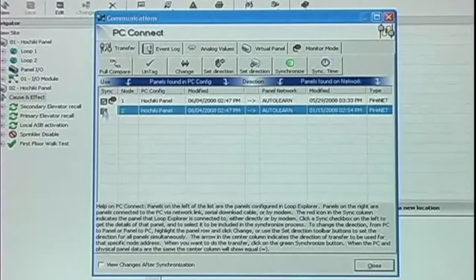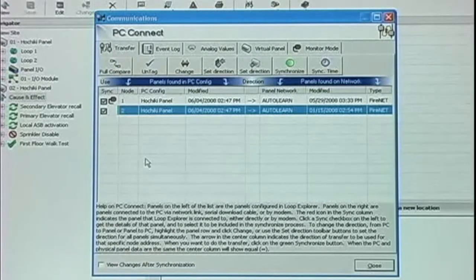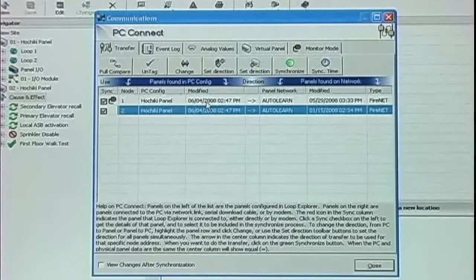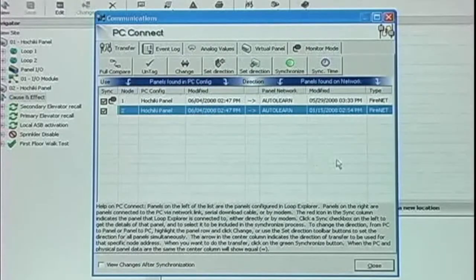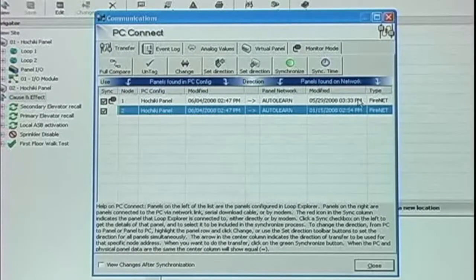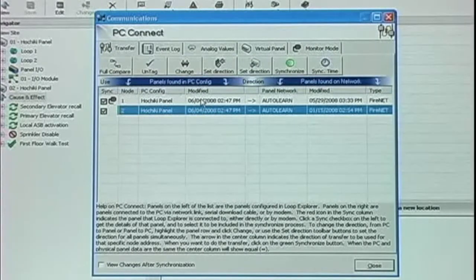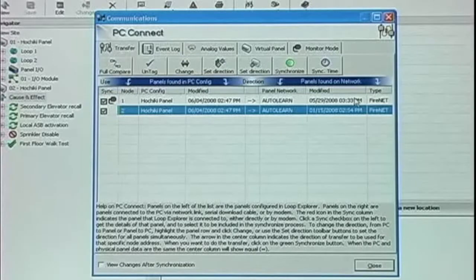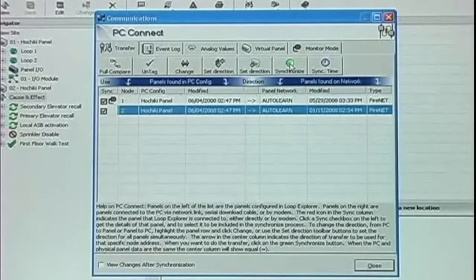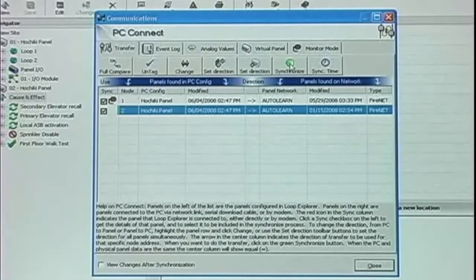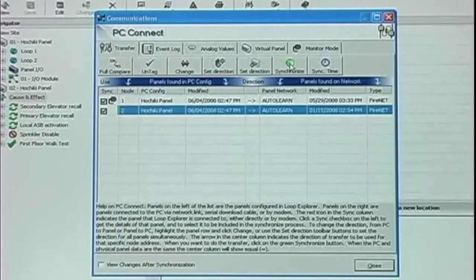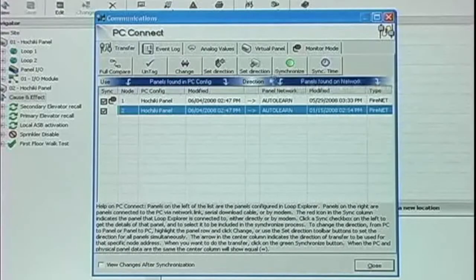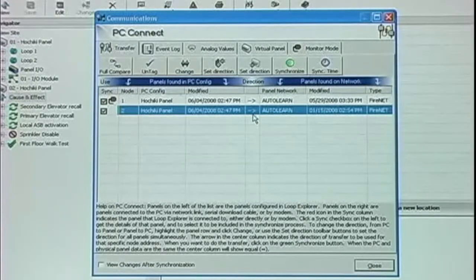When we check the sync box for each of the nodes, Loop Explorer compares the date and time stamp between the configuration in the PC and in the panels. When we click the Synchronize button, Loop Explorer will automatically send the data in the direction indicated by the arrow.